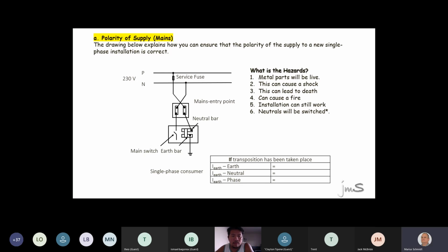No. There are line companies across New Zealand. If someone livens an installation and they don't do the test and polarity is swapped, what happens to that linesman? Gone, fired. They don't get second chances. So that becomes bread and butter. You guys check polarity all the time. So if you don't check polarity, what happens? Metal parts become live. Guys, do you think that has ever happened before? A lot. Swapping polarity around.